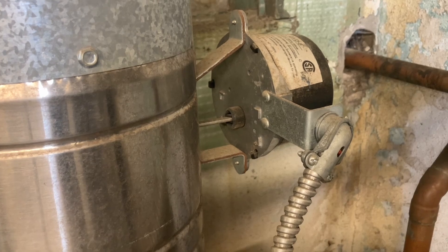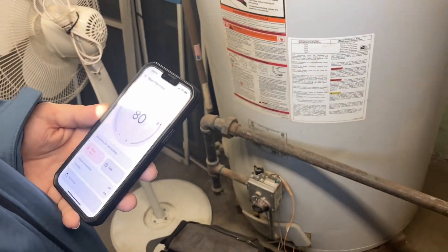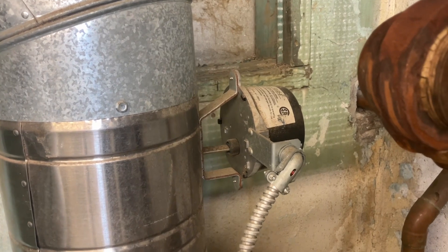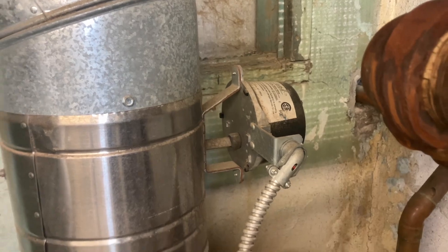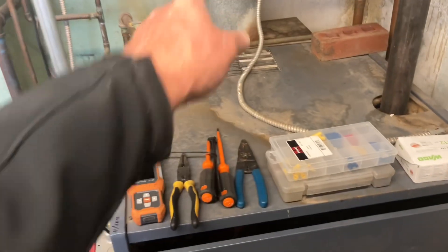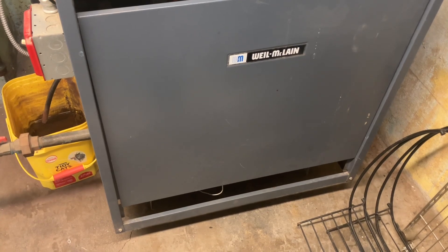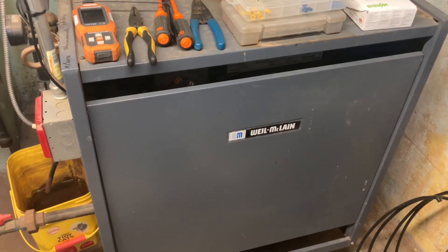Now let's fire this bad boy up one more time — raise the temperature again. The vent damper is going to call to open, and once it's open the end switch will be closed. As long as the pressuretrol, the low water cut-off, the rollout switch, and the spill switch are all closed, we'll have ignition — and there we go, easy peasy.